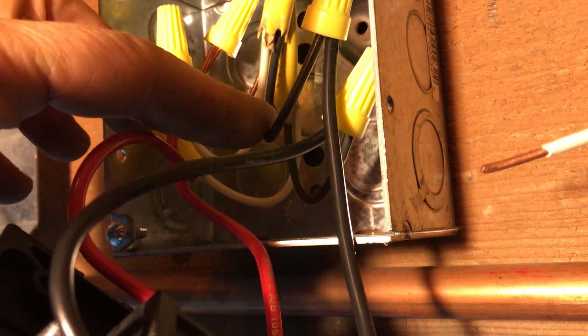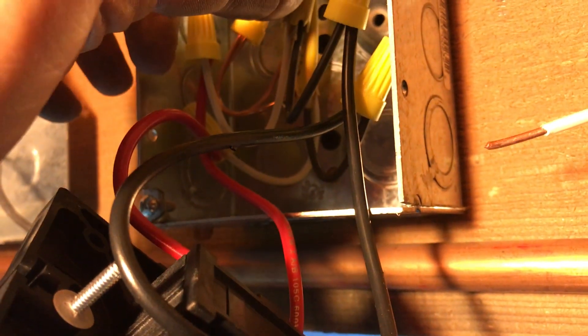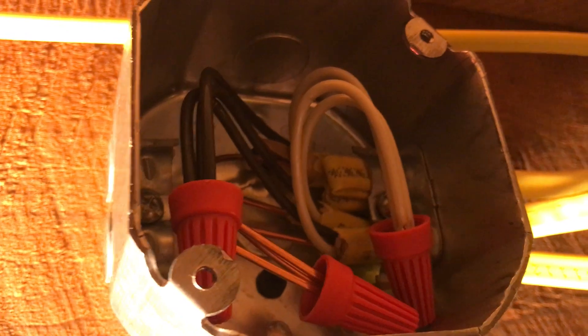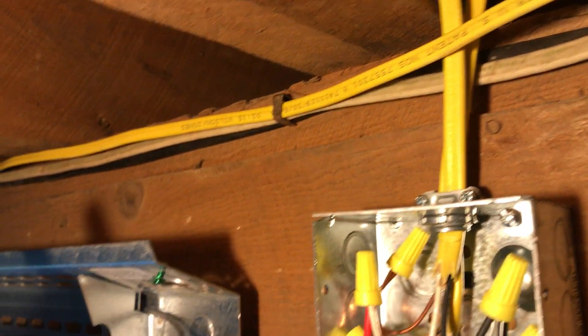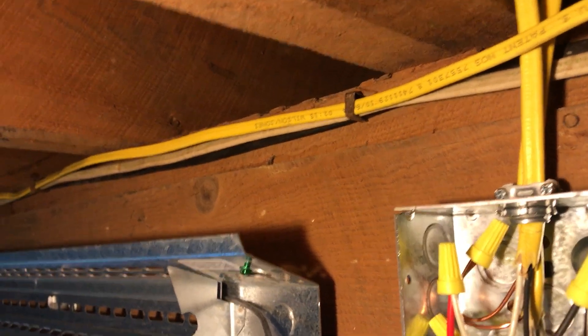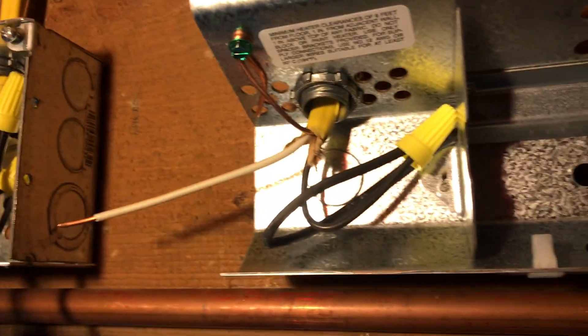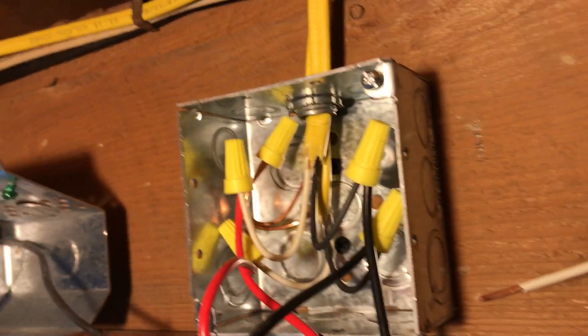Then it's into the top one going through the box towards me, and that goes into the top here where they all get connected. You have to connect all three blacks, all three whites, and all three grounds. That brings it back to the heater over there—it goes to that box and to this heater right here. It feeds both of those heaters.